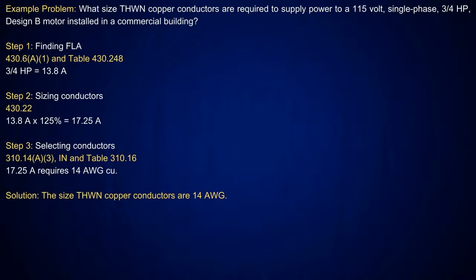And that's why we break this down, so you know where we're going to get these amperages. So in this case, for that 3/4 horsepower single phase 115 volt motor in table 430.248, it's going to tell you it's good for 13.8 amps. And then I go to step 2, and you look at 430.22, and where I have a single motor there, you have to take it at 125%.